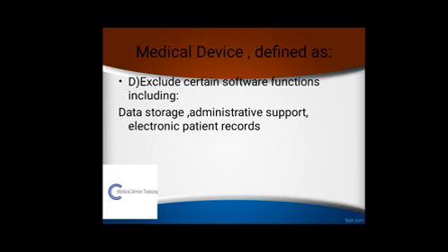D. Excludes certain software functions, including data storage, administrative support, and electronic patient records, because in the above software they aren't used to treat, diagnose, cure, mitigate, or prevent disease. Maybe if I explain more about medical software, you will be able to understand the difference between medical and non-medical software more easily.